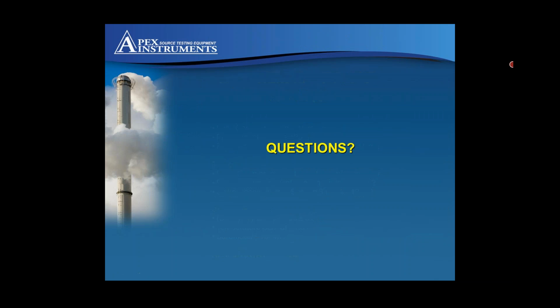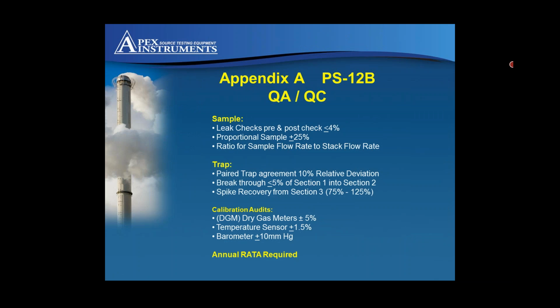The last screen covers the QA/QC: your leak checks and the 4% proportional sampling we talked about. These are all in the PS12 document under the QA/QC section. The calibration audit mentioned at the bottom is the quarterly audit I mentioned, which is built into the software. Once you do that, you do your annual RATA, and that's pretty much it for maintaining the system.